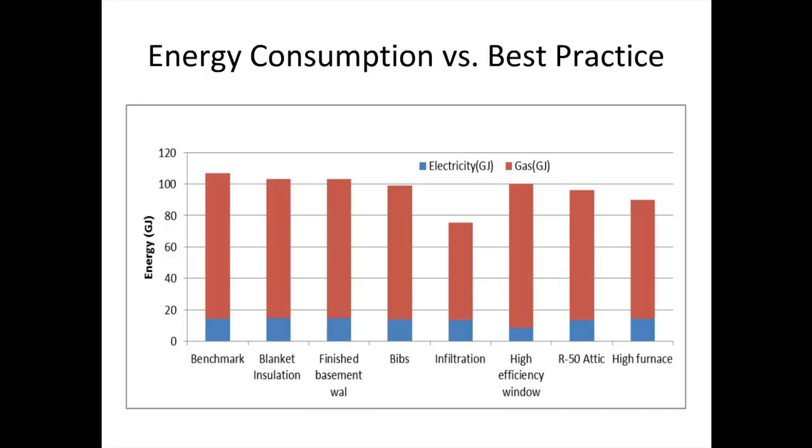As you make it airtight, though, the one thing they do have with the furnace is a constant volume of fresh air coming in to their homes, which is just a cheap, $300 to $500 fan that you install that brings air into the return ductwork, so that you bring in constant air. Hearthstone did that and actually found that it pressurized the home slightly when exhaust fans weren't on, and that actually did quite a bit to reduce radon issues. They went from about a 20, I don't remember the number. It was something like 10% of their homes had to have radon mitigation.